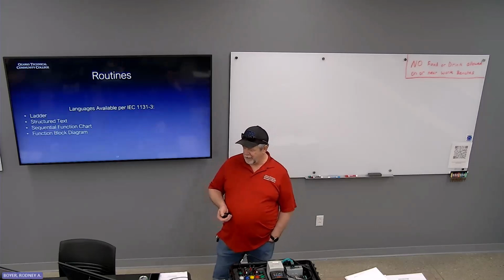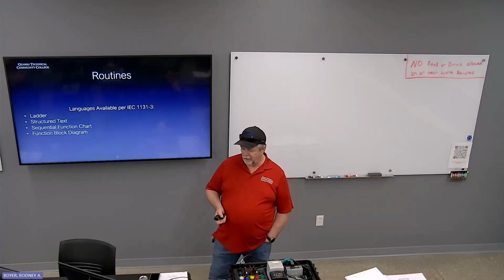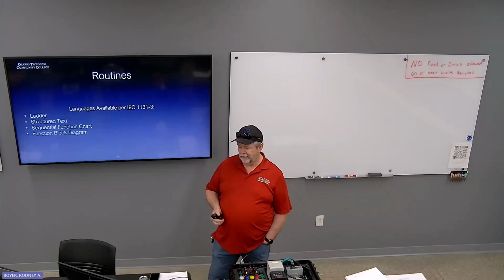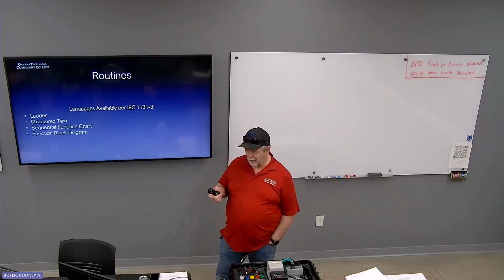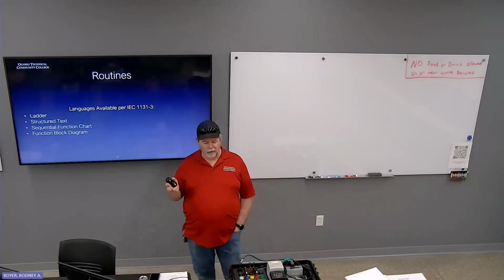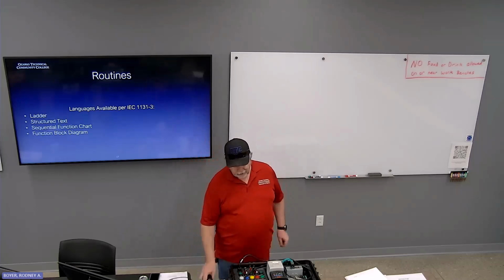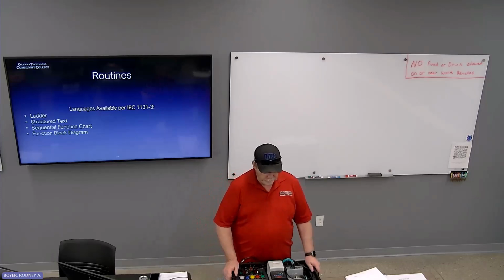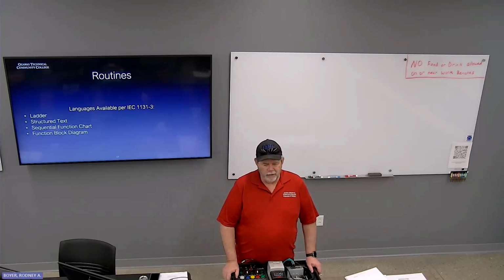Available languages per IEC 1131-3: ladder, structured text, sequential function chart, function block. Again, ladder is by far the most common, function block is number 2. For whatever reason, Rockwell decided that some of the functions that you can use in Logix 500 on a SLC or MicroLogix, specifically the scale instruction, would not be available in ladder on 5000. Why, I don't know.